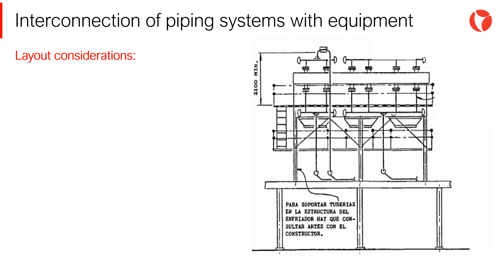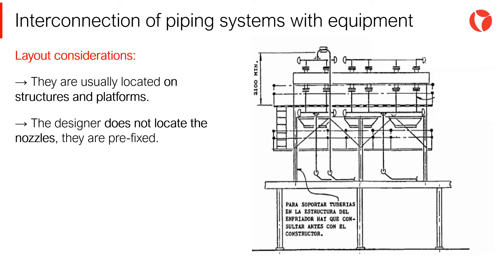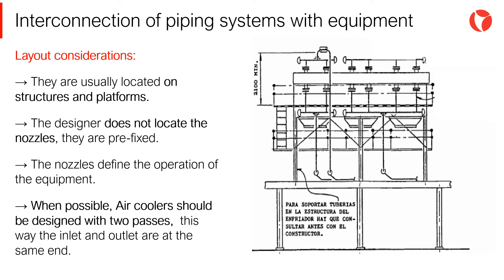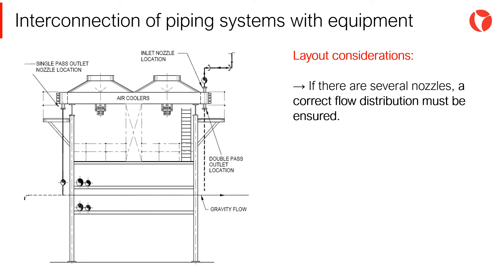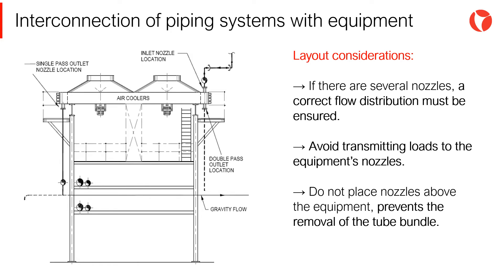The main layout considerations for air coolers are: they are usually located on structures or platforms. The designer does not locate the nozzles — they are prefixed. The nozzles define the operation of the equipment. When possible, air coolers should be designed with two passes, so that the inlet and outlet nozzles are at the same end. If there are several nozzles, a correct flow distribution must be ensured. Avoid transmitting loads to the equipment's nozzles, and do not place nozzles above the equipment so as to prevent the removal of the tube bundle.